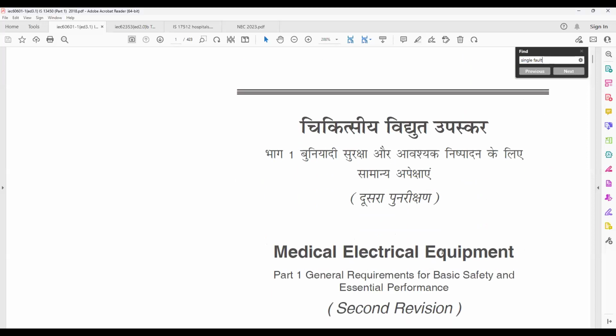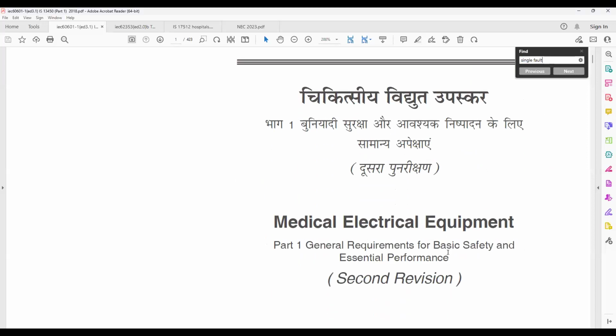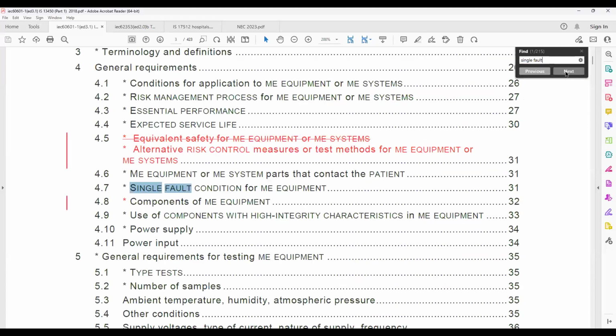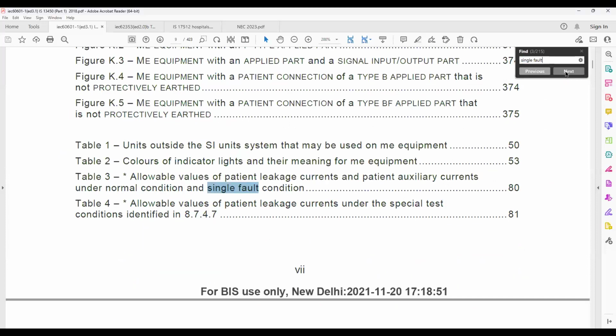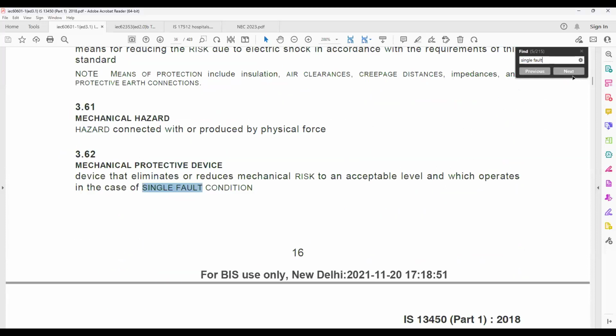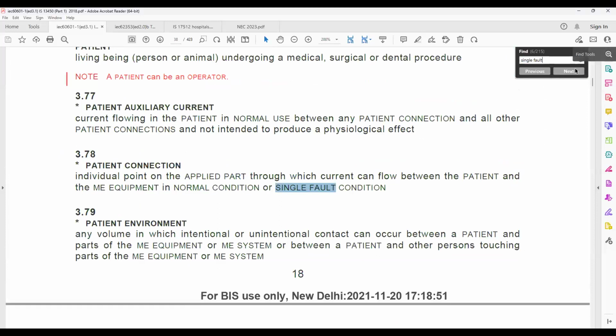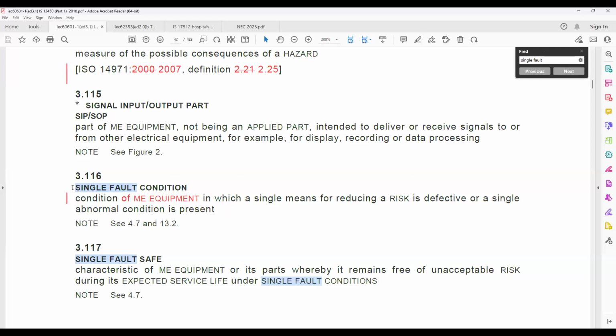Single fault. This one is medical electrical equipment. That means the equipment which is used in a hospital has to satisfy these requirements. You just see single fault condition. About 200 times single fault conditions are explained. I'm just skipping each one by one. Just let us look at what this single fault condition is. Condition of medical electrical equipment in which a single means for reducing risk is defective or a single abnormal condition is present. In the sense, medical electrical equipment often should work under single fault condition. Now the electric supply to the medical equipment shall be able to handle it. And if it cannot handle it, you end up with fire.